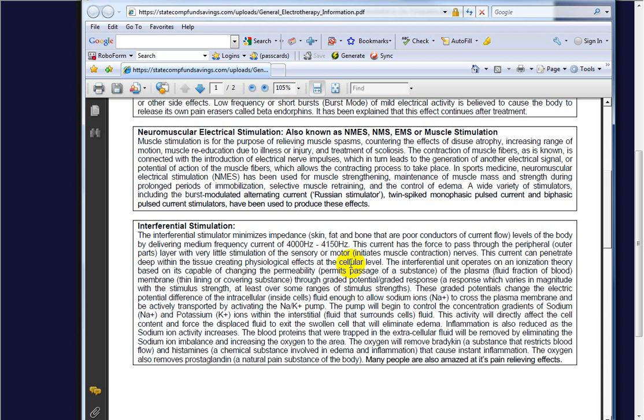Interferential works a little differently. With a TENS device, you'd use certain electrode placements along the nerve path. With Interferential, you surround an area and create a crisscross with the lead wires, so that one lead wire splits into two pins. You might be top left and bottom right — connecting the lines of one half of an X. And the other wire is bottom left and top right.